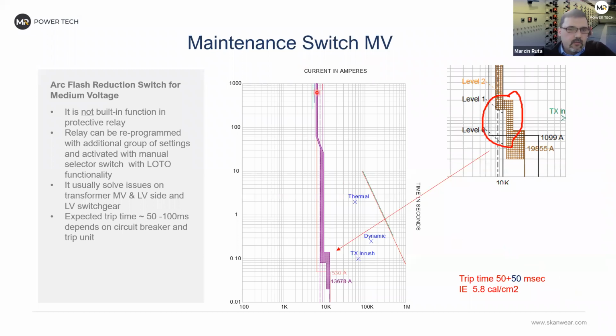we are back to the example with the medium voltage relay, but in this case with what are called adaptive settings. This is the maintenance switch, or arc flash reduction maintenance switch, on for the medium voltage. Physically, what we do is reprogram the protective relay on the medium voltage side with an additional group of settings. This will be activated by the lockout tagout maintenance switch, which is physically a switch, but needs to be locked out and tagged out. And it looks the same because it is the same settings that I used before. But the intention is, as with ARMS, to use it only during maintenance activities. And this will reduce energy a lot, in this case below 6 calories per square centimeter, assuming that in total it would take something around 100 milliseconds. And once we are done with our maintenance operation, we reverse it back. So Martin will probably explain a bit more about the procedure, but this will be one of the solutions.